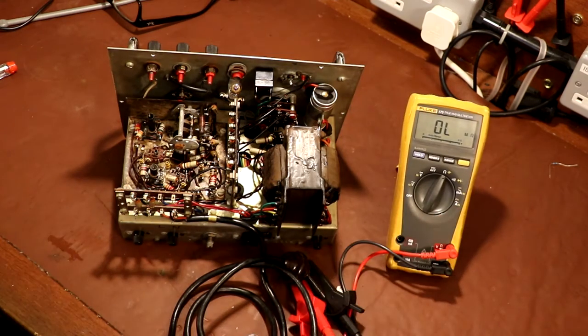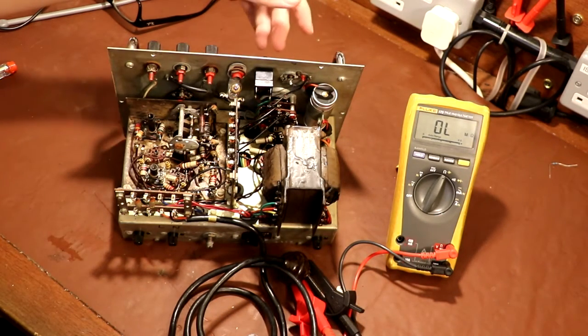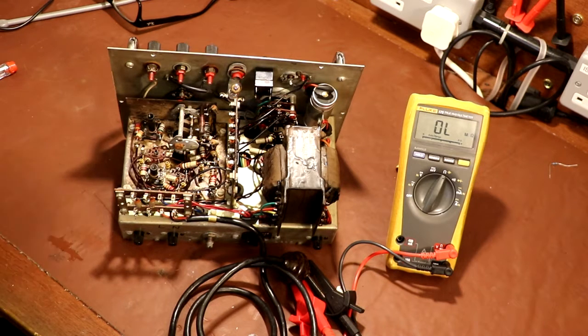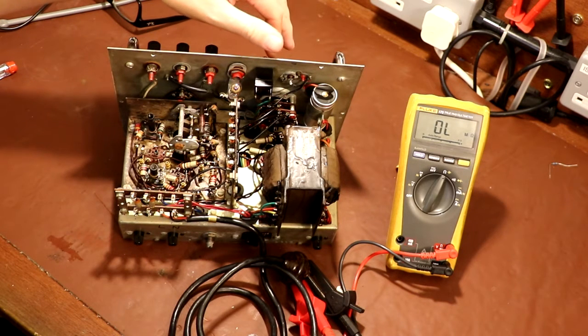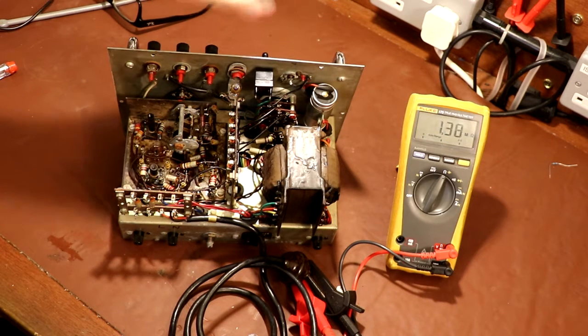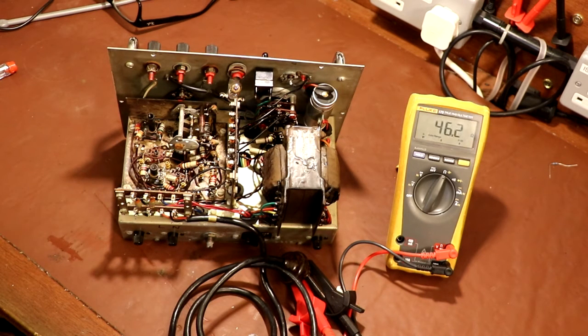So what we actually need to do is make sure the thing is switched on, and I'd expect it's anywhere between maybe 50 and a few hundred ohms. Not exactly sure, let's find out. Okay, so we've got 46.1 ohms. That's in the ballpark, probably slightly lower than I'd have expected, but I'm not going to panic. Certainly it's not open circuit, so that's a good sign, isn't it?